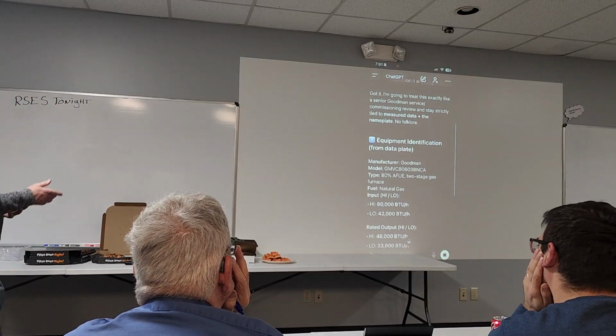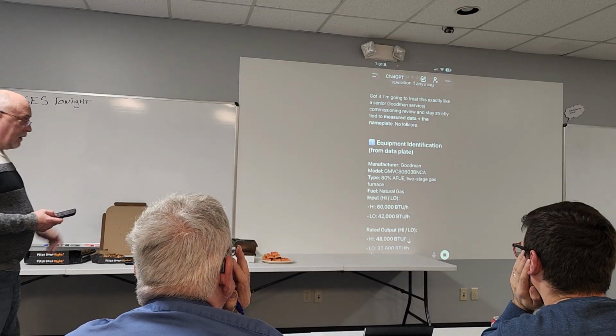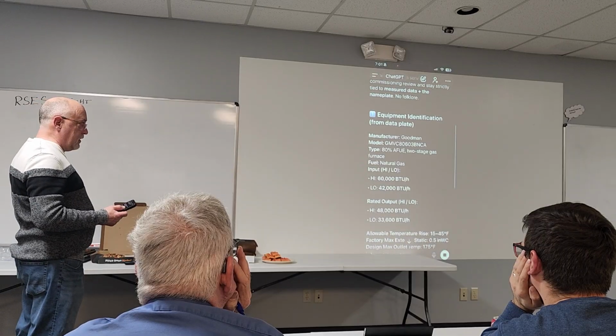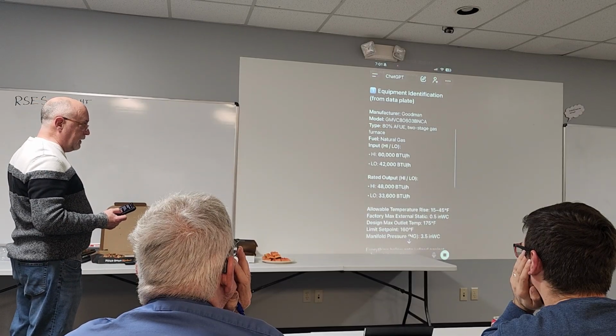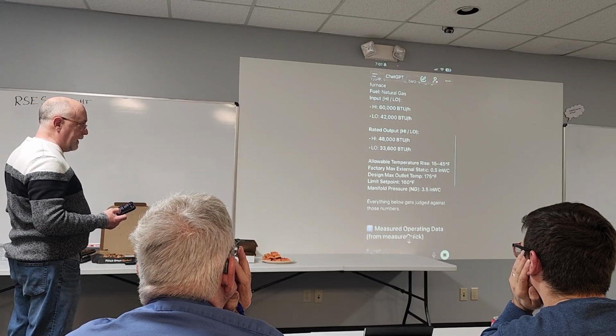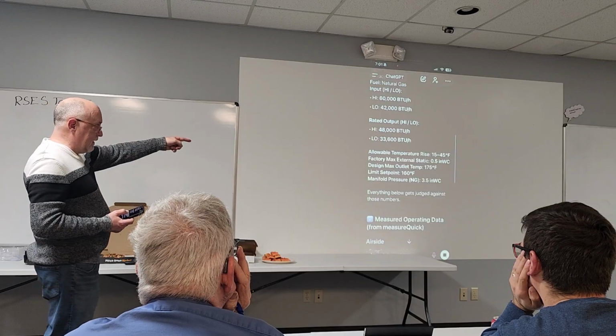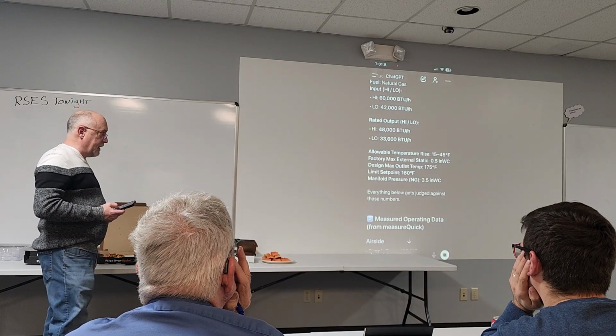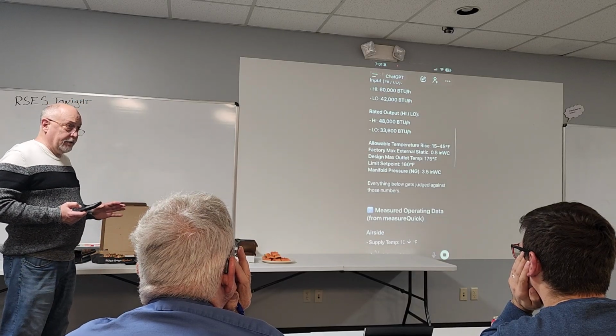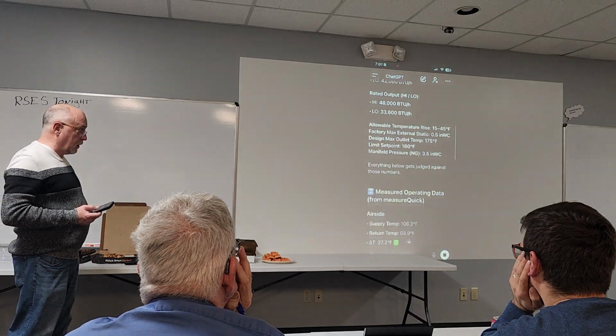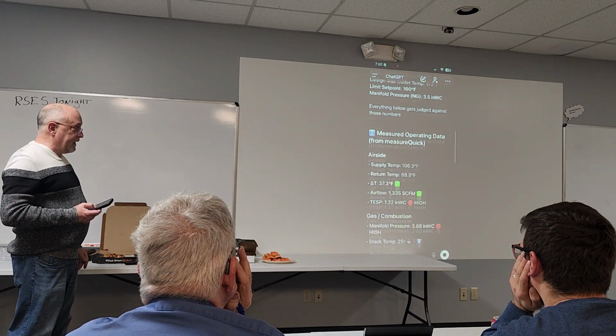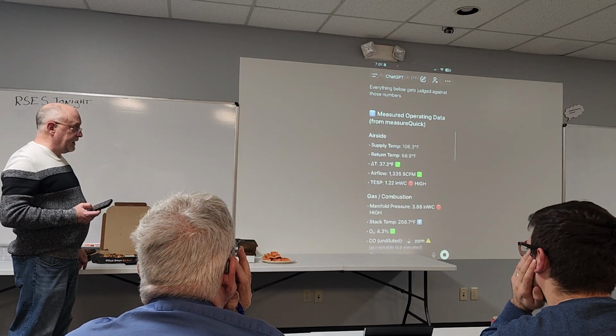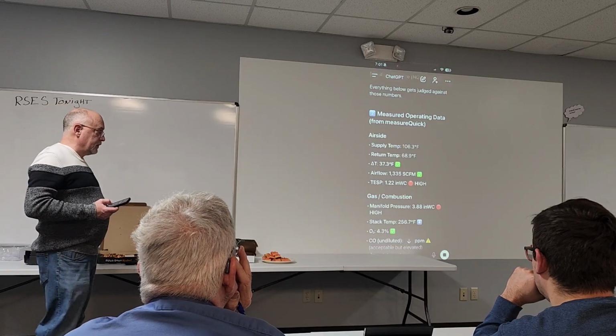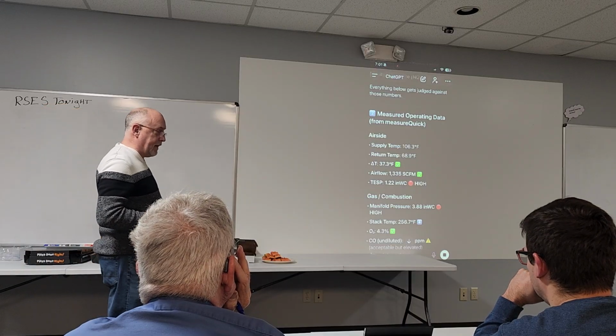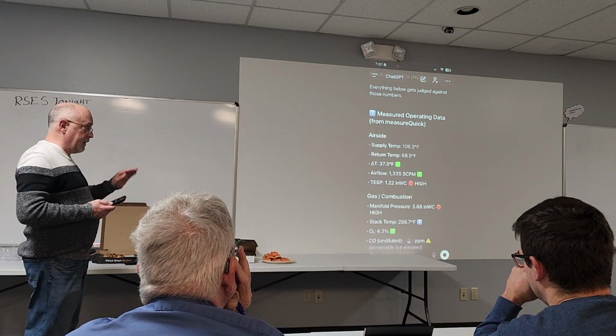So, off the equipment data tag, it pulled in the model, 80% two-stage, high 60,000, lows 42,000, rated input, rated output, the temperature rise, the max design outlet temperature, the limit set point, all that's on the data plate for the furnace. So now it's got a lot of context to work with. Measure quick operating data, it's telling us the delta T is great, airflow is 1335 CFM. Now, here's another thing to stop and think about just for a minute.